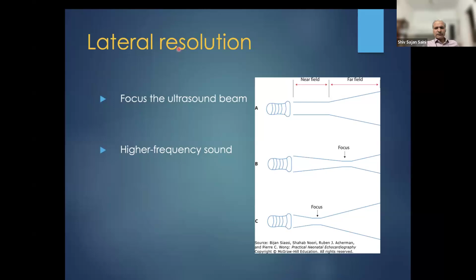So this is how we can adjust the focus. Once we have this visual display of the sector from the phased array probe, this is a sector, and there is the cursor orientation marker, and this is the depth. These small dots show the depth. Every machine will write here 5 centimeter or 4 centimeter, etc. It is equivalent to the depth, and there is the focus. The middle point is the focus, and it has a kind of box and whisker, a central dot and a whisker.